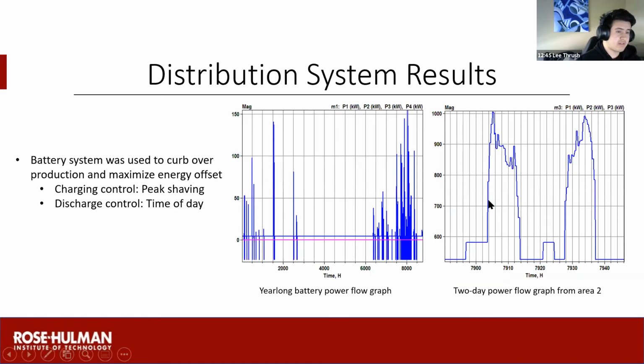In order to maximize the energy offset produced and used through our batteries, we wanted a set of controls that could trigger to charge to curtail overproduction, and that would trigger to discharge in a controlled manner. We found that using peak shaving for the charging control best curtailed the overproduction while maximizing the energy offset from the solar production. We then used a time of day based control for the discharge to maximize the amount of hours we can produce power for the batteries.